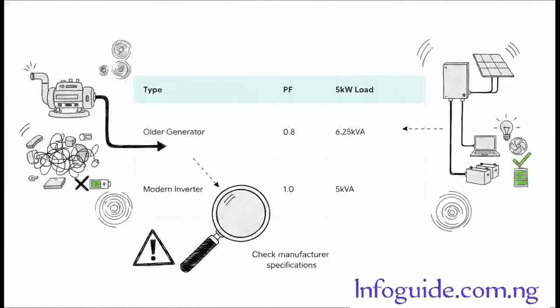Now this is exactly where the rubber meets the road. Historically, and you still see this a lot with older UPS systems or standard gas generators, the power factor sits at about 0.8. What does that mean? Well, to run exactly 5 kilowatts of appliances, a 5 kVA generator just won't cut it.